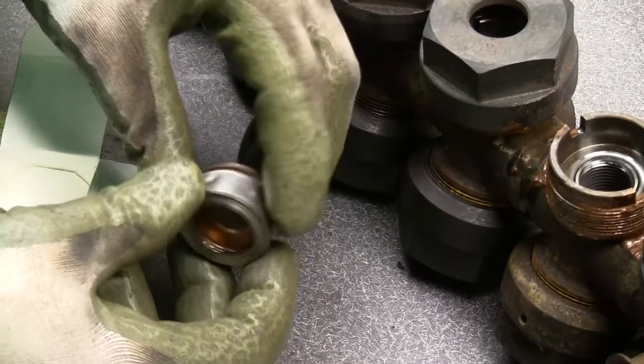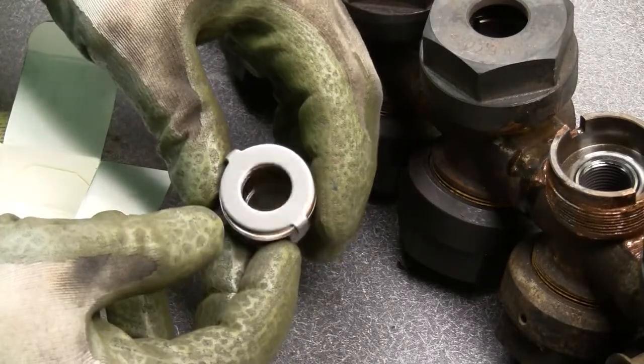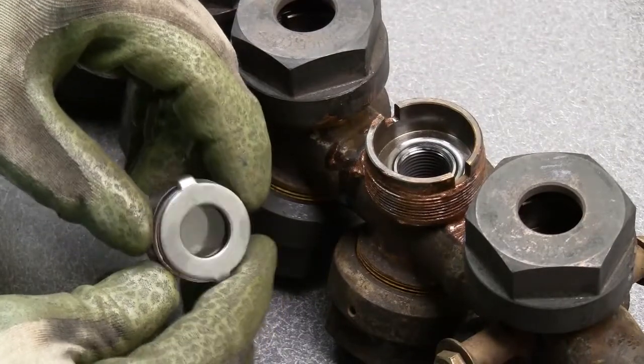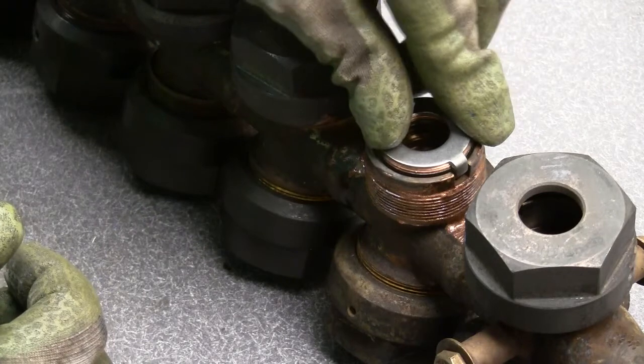Inspect the new glass module to assure the gasket is centered. The custom-engineered gasket employs high-density graphite to resist cold flowing. Align the lugs and make sure the dimples are not aligned with the slots. Place the new glass module in the body. Clark Reliance uses V1-grade .030-inch mica, the best available, to extend gauge life.